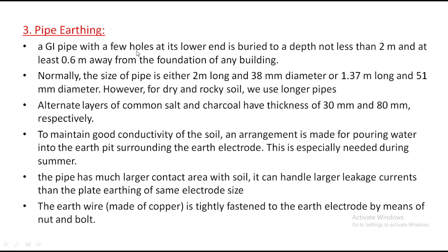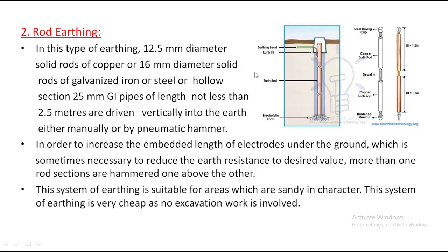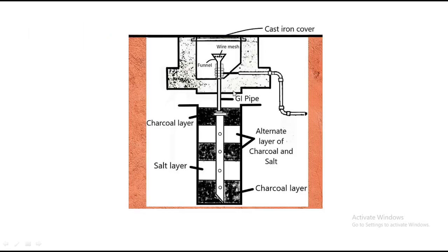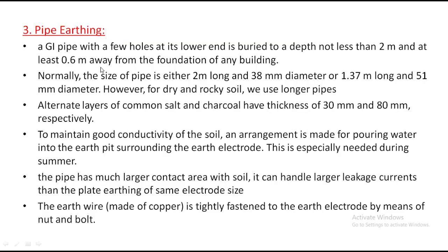Okay, a GI pipe with a few holes at its lower end is buried to a depth of not less than 2 meters, at least 0.6 meters away from the foundation of any building. This length must be 2 meters. From this point to this point is 2 meters, and 0.6 meters away from the foundation. Normally the size of the pipe is either 2 meters long with 38 mm diameter or 1.37 meters long with 51 mm diameter. However, for dry and rocky sites we use longer pipes. Understand? So this is the length and this is the diameter we have to use.